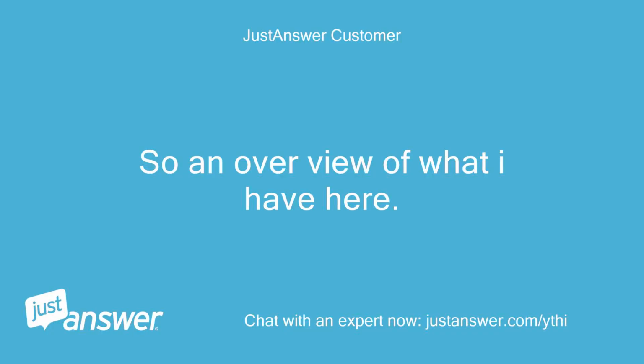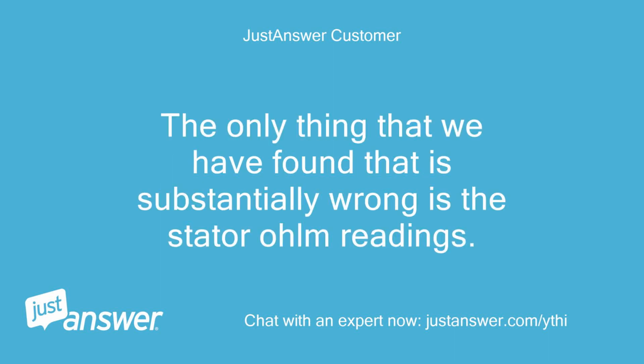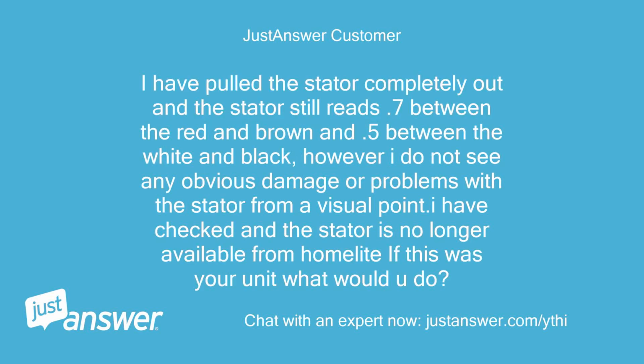So an overview of what I have here. The only thing that we have found that is substantially wrong is the stator ohm readings. I have pulled the stator completely out, and the stator still reads 0.7 between the red and brown and 0.5 between the white and black. However, I do not see any obvious damage or problems with the stator from a visual point. I have checked and the stator is no longer available from Homelite. If this was your unit, what would you do?